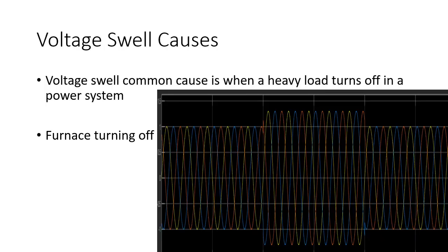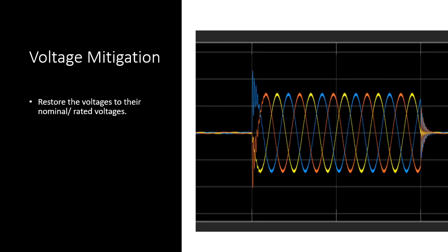What causes voltage swell? It's essentially the opposite of voltage sag. A common cause is when a heavy load turns off in a power system — for instance, a heavy furnace suddenly turning off due to some issue, causing a voltage swell. Another example for understanding, though not exactly a swell because it's not momentary, is the Ferranti effect in power transmission lines — where you need 230 volts but receive 250 volts.